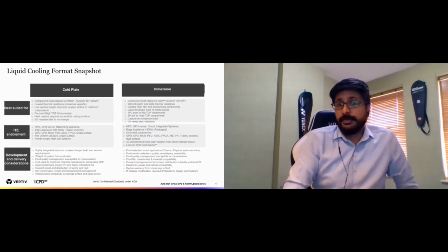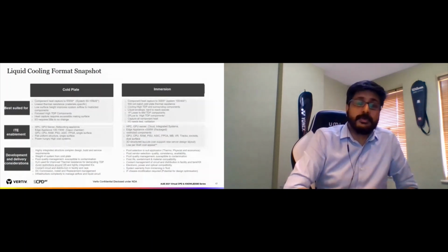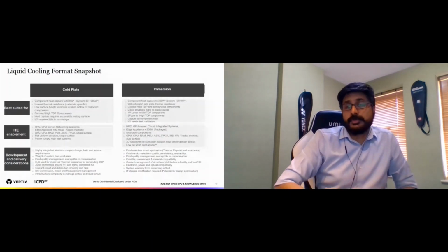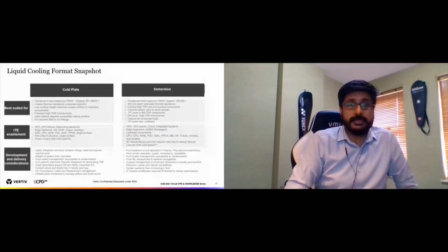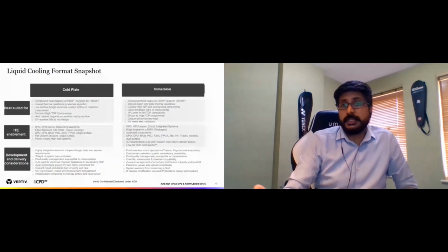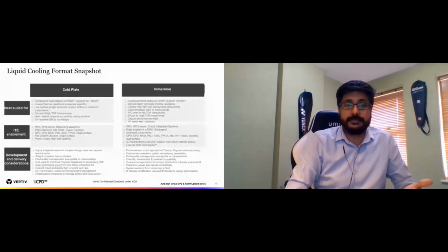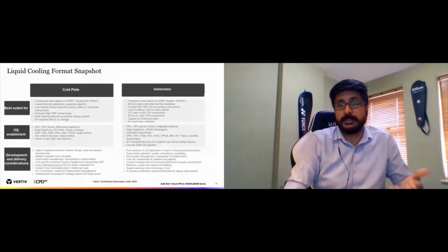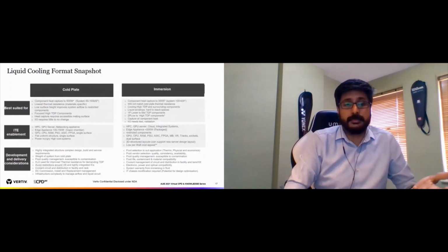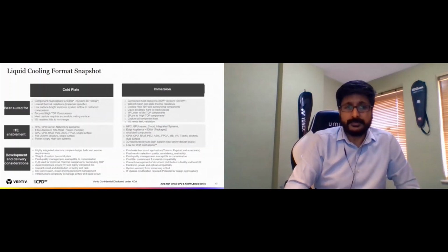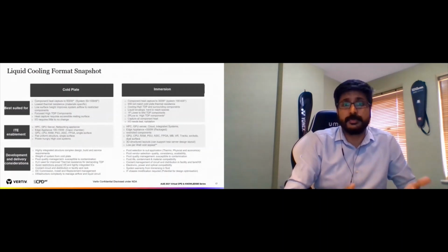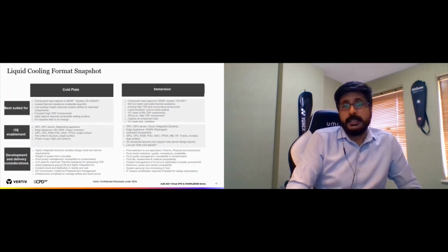From that point of view, immersion becomes slightly advantageous because the entire system is getting cooled, but then comes the complexity of how you can service this, and also the type of components that can be used within immersion and liquid cooling, and chip cooling as well. So immersion has to have specific kinds of components that can be immersed into the dielectric fluid, but on chip cooling, all you have to have is a component or a plate that can be sitting on top of the GPUs or the CPUs as well. So there are advantages and disadvantages of cold plate and immersion. So it depends on the application that we are trying to use.